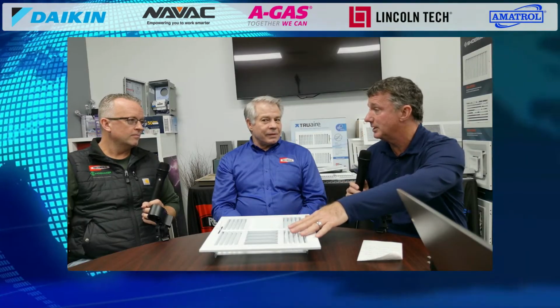Yeah. I spent quite a few years at the distributor level doing technical training, and also a lot of technical support for one of our major manufacturers. In that, I was able to learn a lot about system capacity and airflow when we moved into constant airflow blowers. If we look at a modern high efficiency system, we're likely going to have an inverter outdoor unit and a constant CFM, or constant airflow, ECM blower. When we start changing the airflow, like shutting those rooms off, in the past all we would do is change the temperature differential. Now we start reducing the airflow. The motor is going to recognize that. But if it has, particularly, an electronic expansion valve using temperature thermistors across the evaporator, measuring TD, the inverter is going to start modulating back down, because it realizes it doesn't have the heat load coming across the coil that it was previously operating at. So now we're going to start reducing capacity, like you had mentioned, simply because of that airflow.